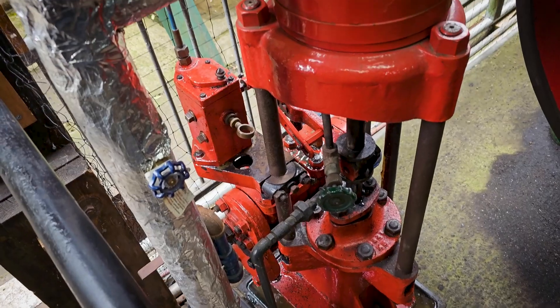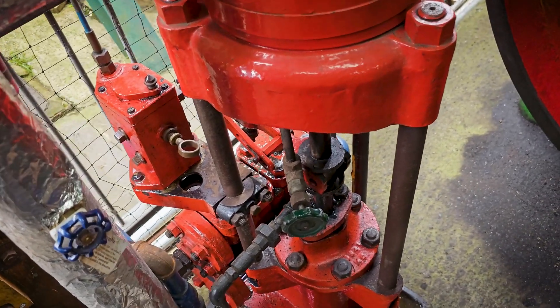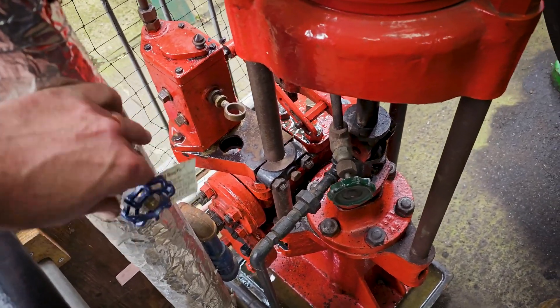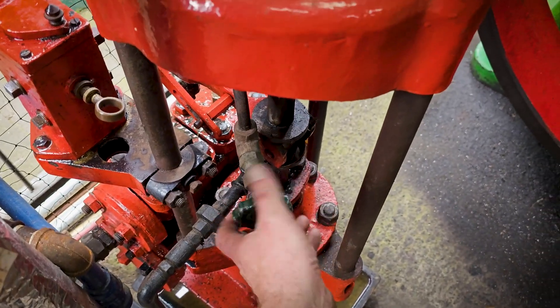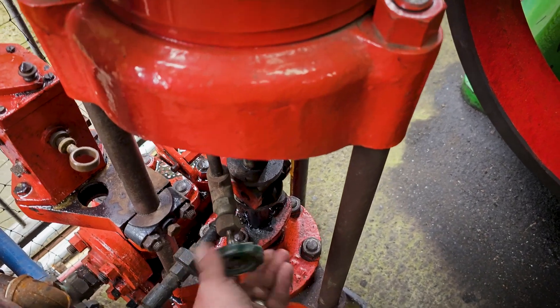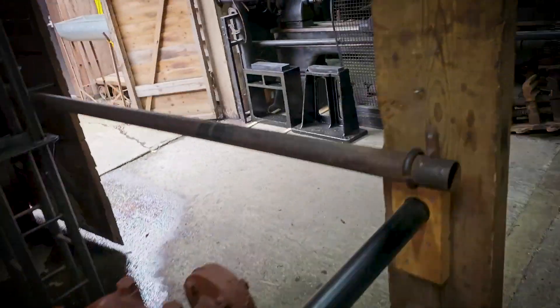One of the things we do here is make sure all our line drains are open - they're various around the museum. There's a cylinder chest drain for this Weir pump. We'll do this all over the museum - make sure no condensate comes into the engines as little as possible. There's another drain cock there, there's another one there. Various line drains.